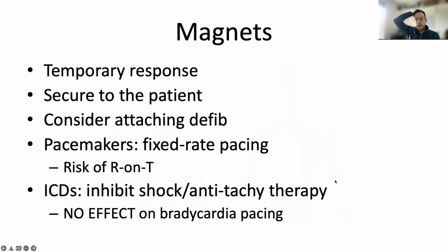It then goes on to try and clear up what the effect of putting a magnet on is. Because I remember being taught that if you put a magnet on, it would completely mess up all the settings of a device, and it would have to be completely reset again from scratch. But that is not the case. So any response is temporary, and when the magnet is removed, it will revert to the settings it was on before.